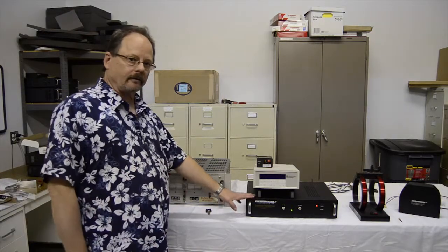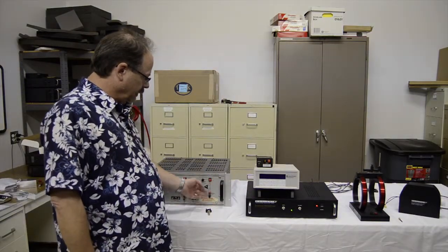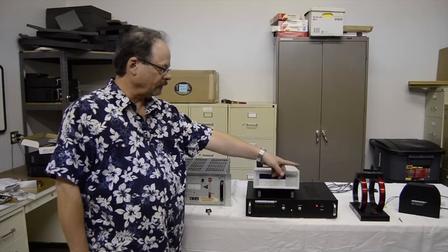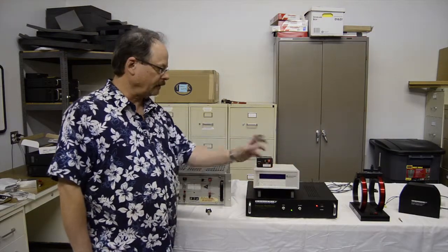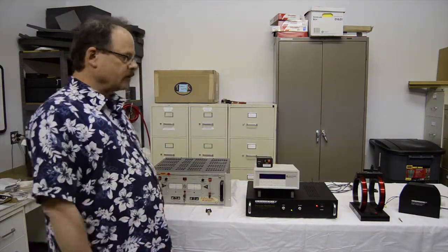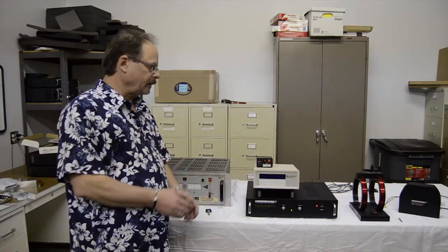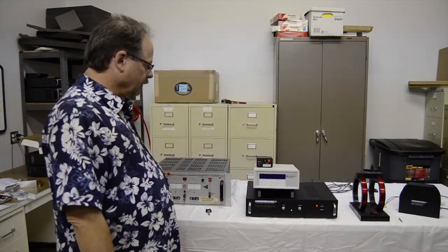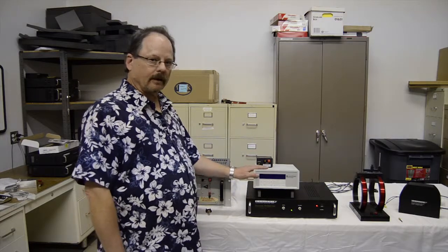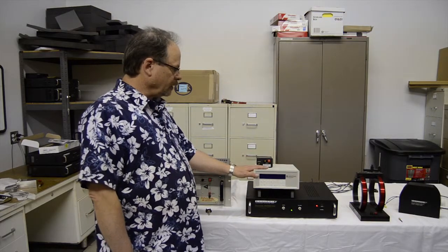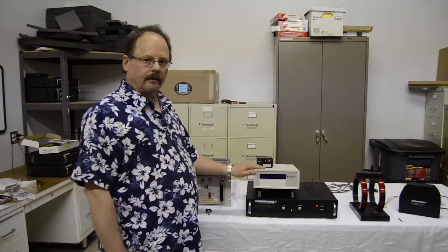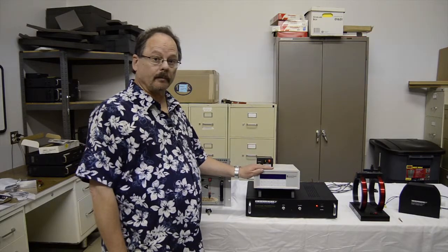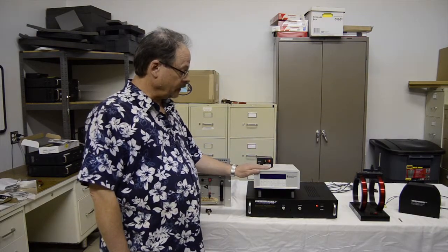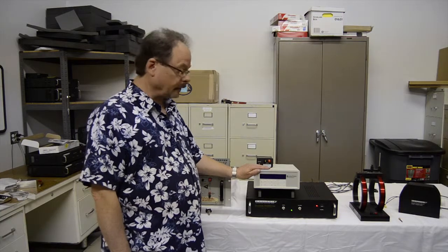In order to set up the experiment, what happens here is that the Radiant tester provides a voltage. It stimulates current out into the Helmholtz coil, which in turn stimulates a field. When we make our measurement, we're very concerned with knowing exactly what that field is. The Lakeshore Gauss meter will directly read the field. The problem is that the wand cannot be in place during the measurement, so the Gauss meter needs to be removed from the experiment.